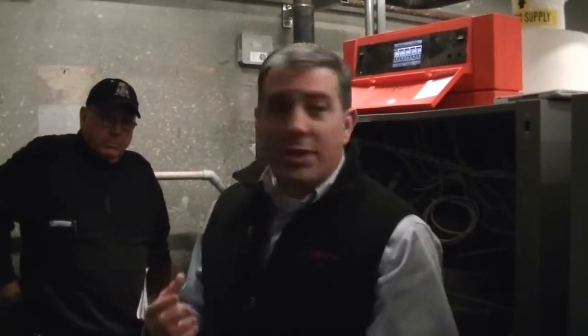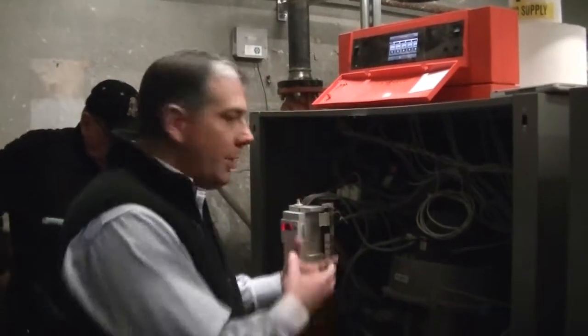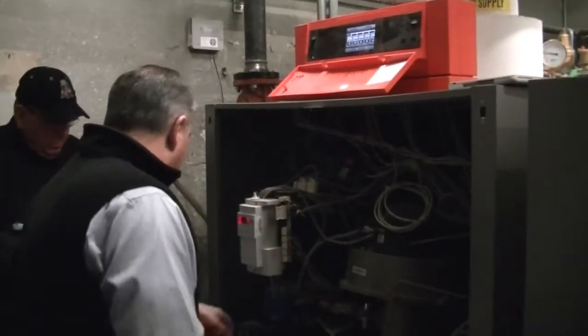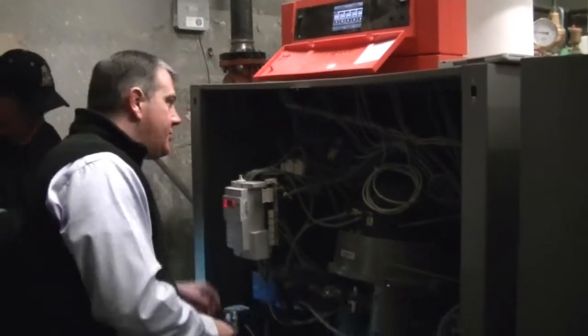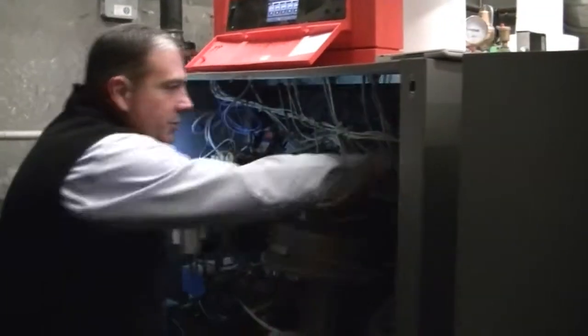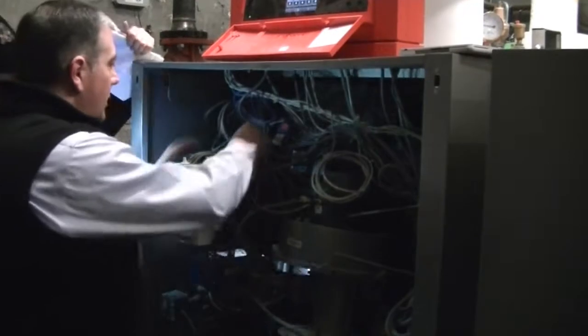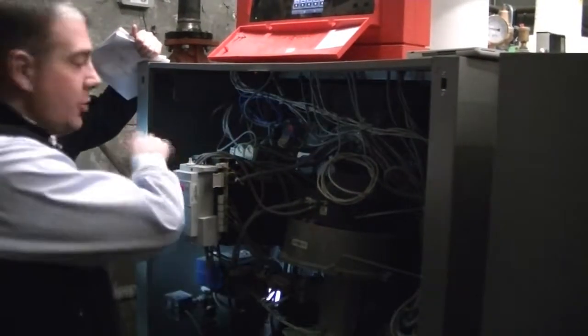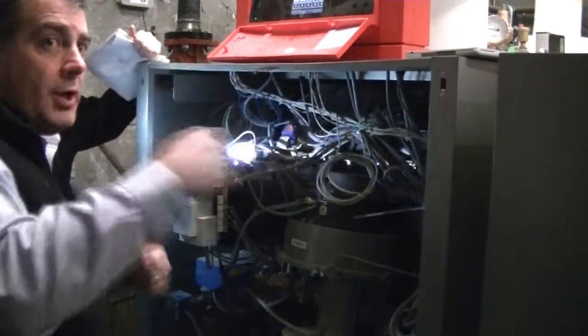Probably a bunch. Because it's a smooth wall stainless steel heat exchanger, it's a single pass heat exchanger. There are no cleanout covers that have to come off for maintenance or for cleaning. This burner door opens up like a cabinet door. So you have a gas union connection on there, you break the gas union connection. There's 4 bolts in the 4 corners on the burner door. You unplug some of the cables and now this whole burner door with the burner on it swings right open.